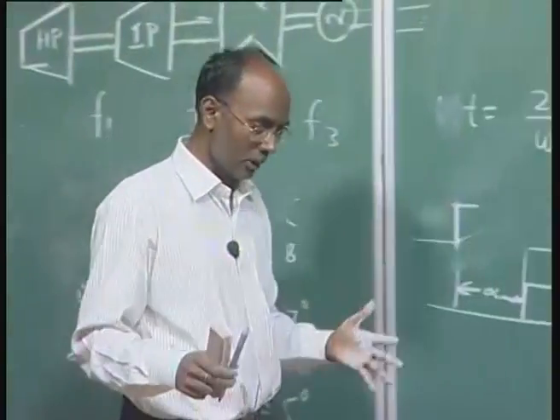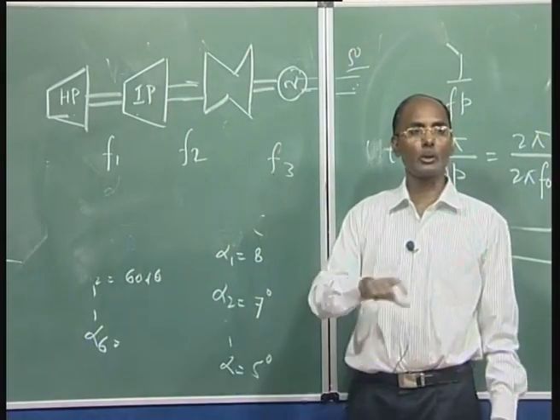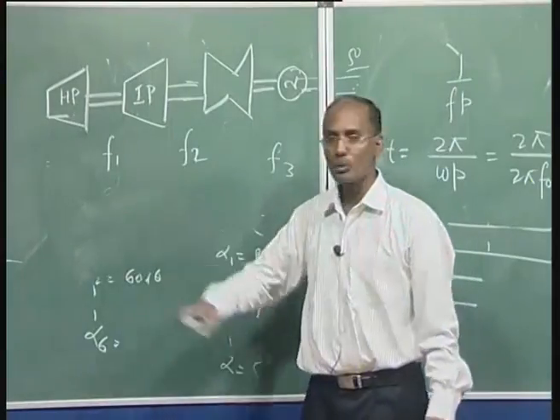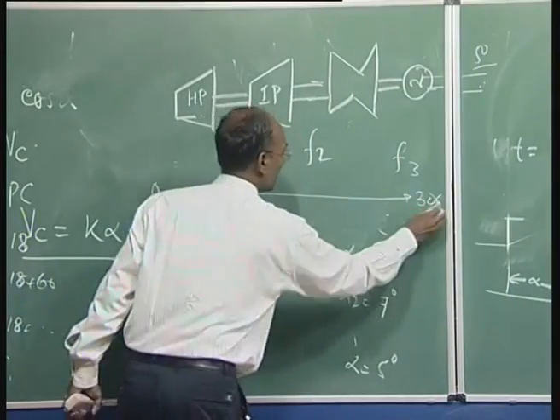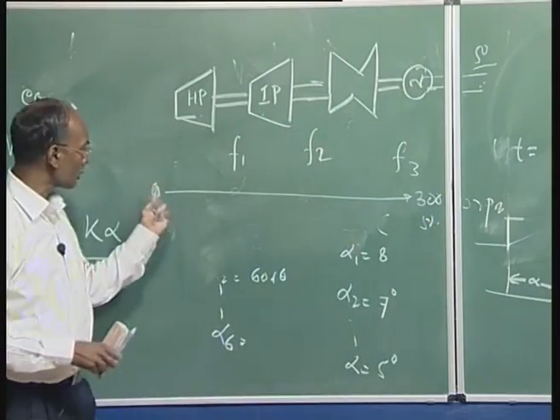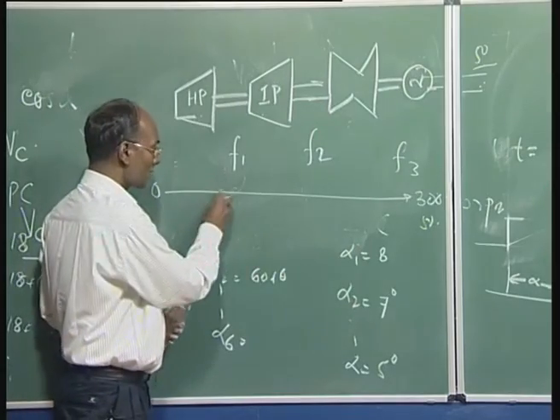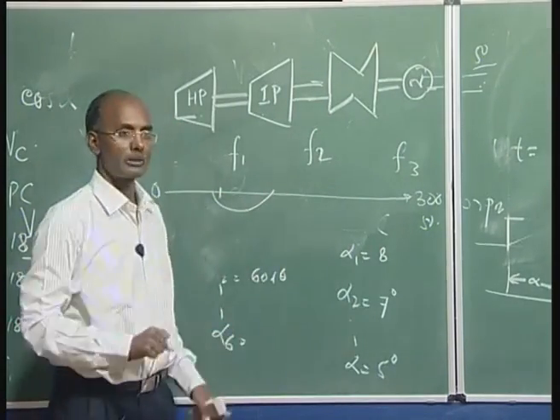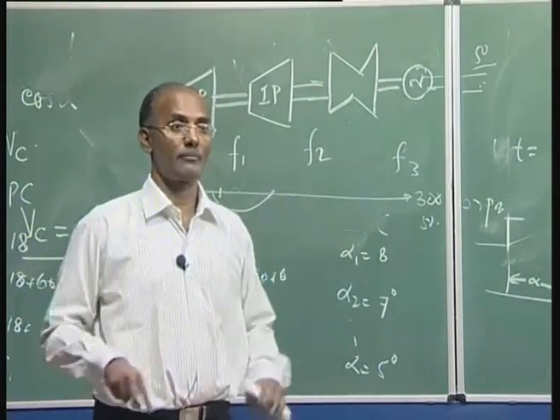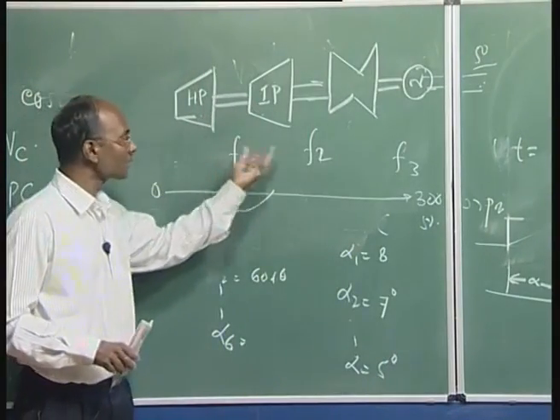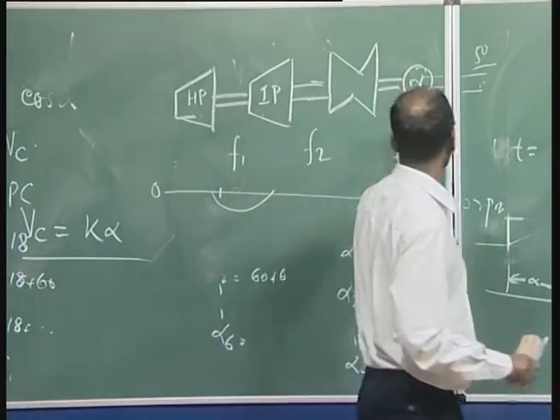In actual power plants, when starting and synchronizing a machine, operators never stop at these critical frequencies. Since 50 Hz corresponds to 3000 rpm, from 0 to 3000 rpm these critical frequencies will be encountered. When these frequencies are reached during run-up, operators quickly pass through them — if they stop at those frequencies, huge oscillations and vibration on the shaft will develop and the machine could fail. These are the critical frequencies; if the frequency from HVDC harmonics matches, huge torque develops and may damage the shaft.